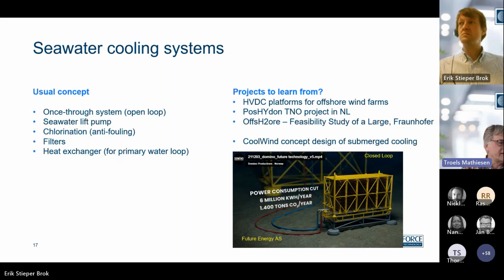So there are some challenges, I will come back to that. But the most used concept of cooling water systems is the once-through, or open loop system, that consists of a lift pump, some kind of anti-fouling chemical dosage, a filter, and a heat exchanger.